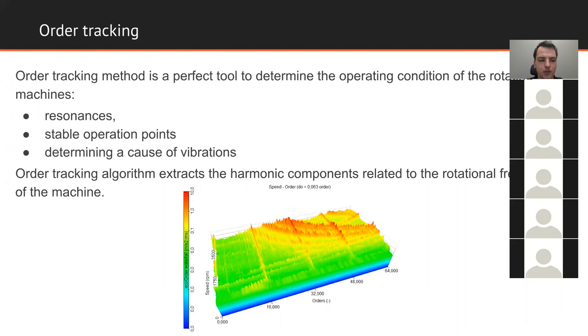With order extraction, we can see specific harmonic components that relate to certain machine faults. The first harmonic usually relates to unbalance of the machine; the second harmonic often relates to eccentricity. For example, if we have a nine-rotor-blade machine, the ninth harmonic relates to errors on the blades. If we have 31 teeth on a gear, the 31st harmonic will show the gear mesh frequency.